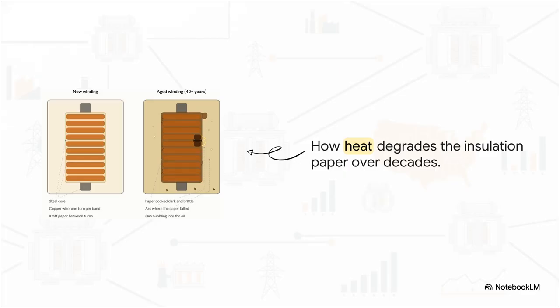And this is exactly where that 42-year average age becomes genuinely terrifying. Inside that tank, you've got copper windings wrapped in cellulose paper and submerged in mineral oil. But over decades of nonstop service, heat physically degrades that paper - it literally cooks in there. The paper gets dark, it turns brittle, and it starts releasing gas into the oil.